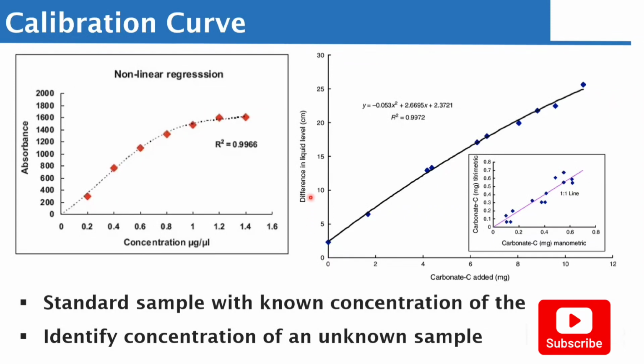So you also have the y-axis and this is the x-axis. You can see there's a 0. So what it means is that this can measure from 0 to what you get here, which is about maybe 10 point something, or let's just say 11. Now, what that means is that the analyzer is able to run anything between this 0 and maybe 11. Anything higher than 11, it cannot measure. Anything less than 0, or maybe minus, it cannot measure.